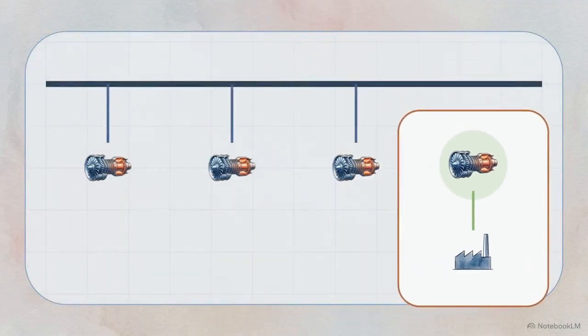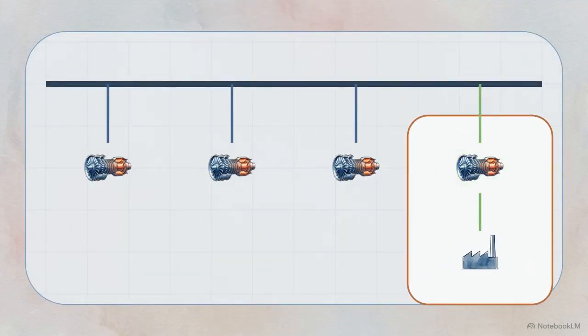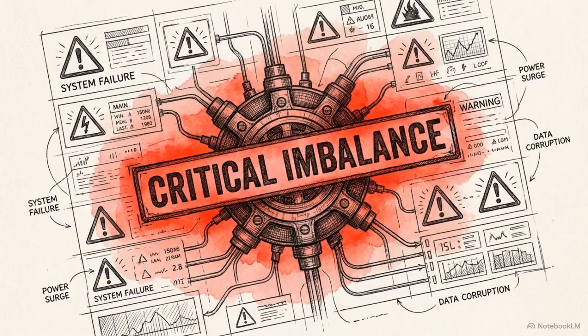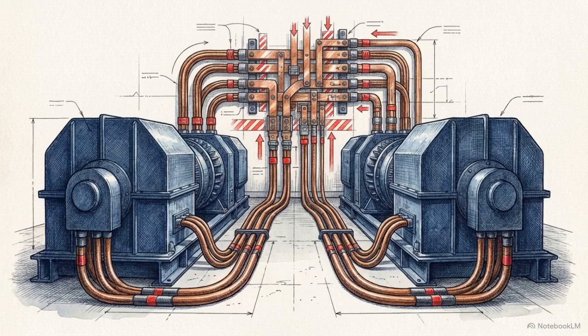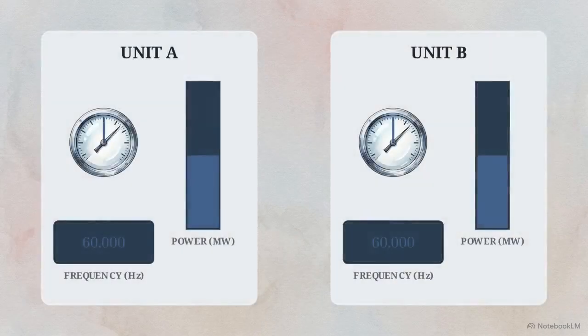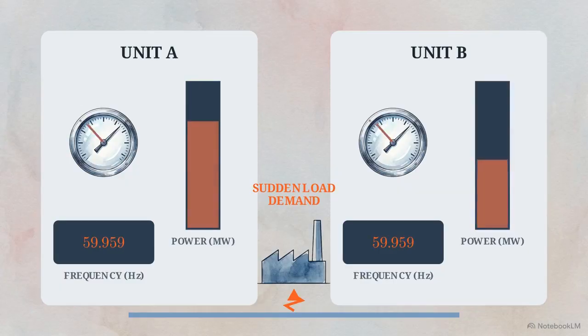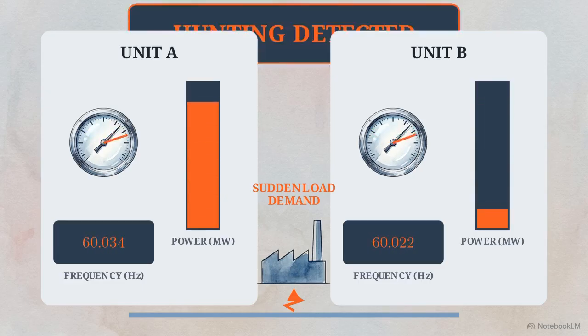But the moment that machine connects to a parallel generation network alongside other turbines, that demand for perfection becomes a severe system vulnerability. Introduce a second, identical LM2500 gas turbine, synchronized and connected to that exact same shared bus. Here, two independent turbine governors try to maintain a 60 Hz target during a sudden load spike. Both detect the deviation and simultaneously attempt to correct it. The result is hunting: massive, uncommanded power swings violently oscillating back and forth between the parallel units.